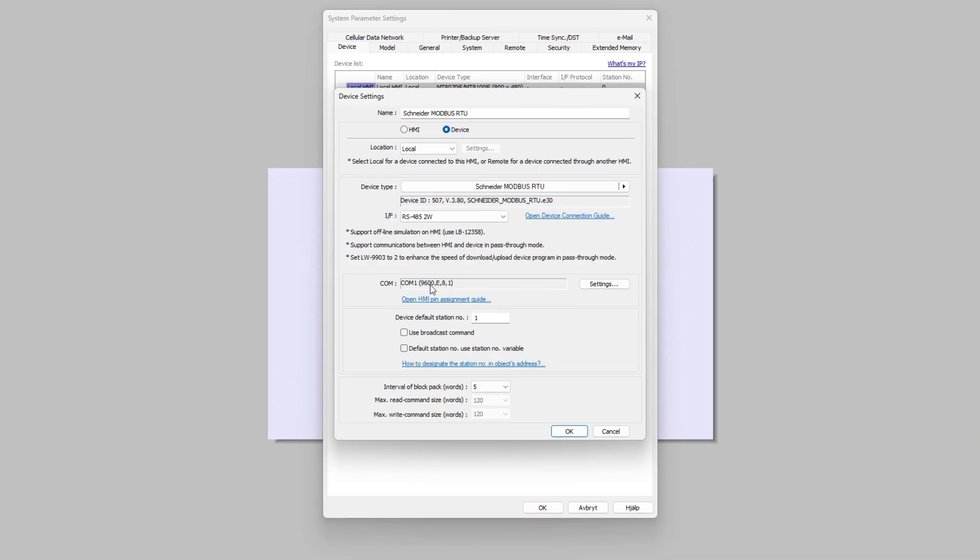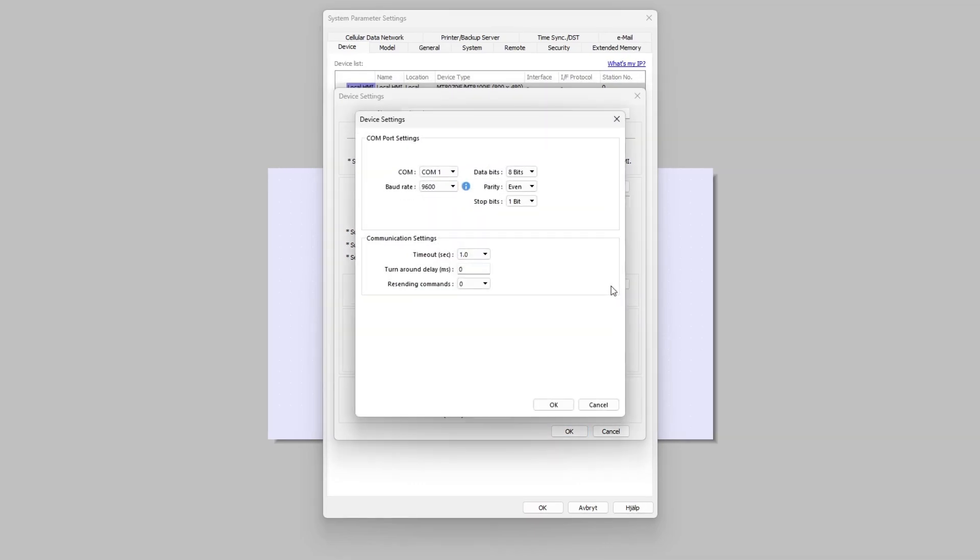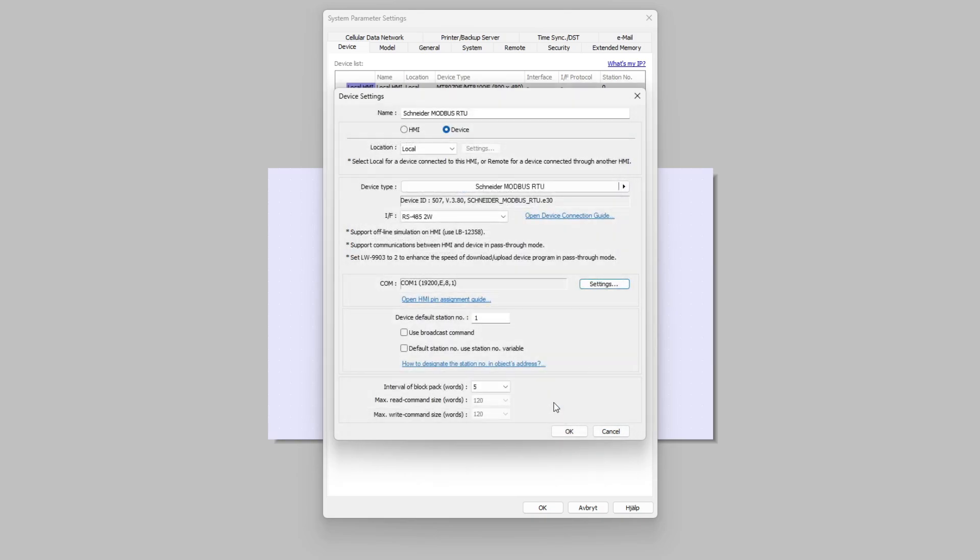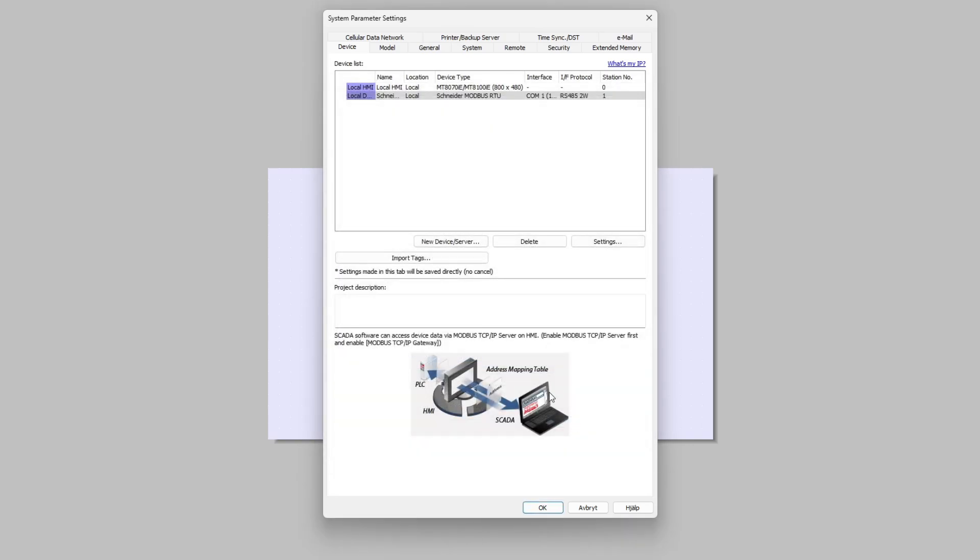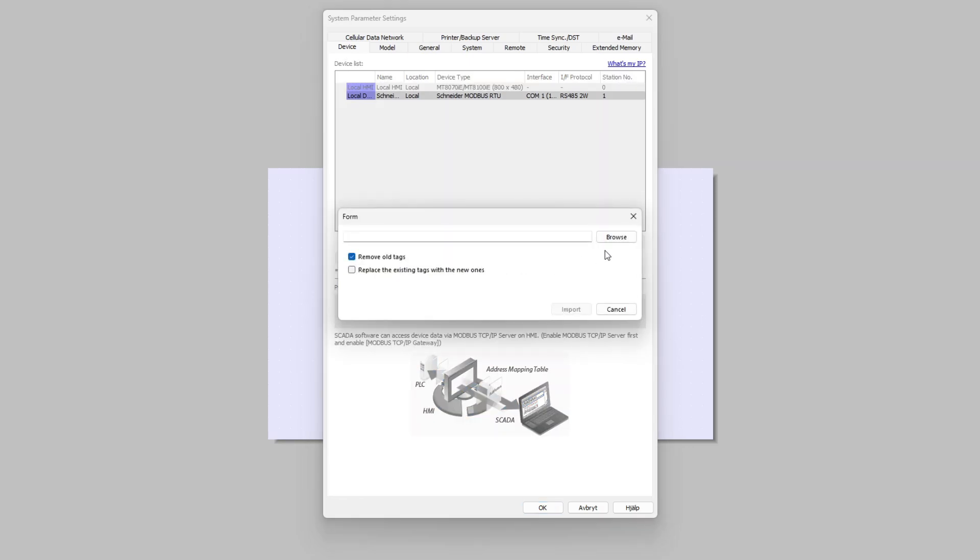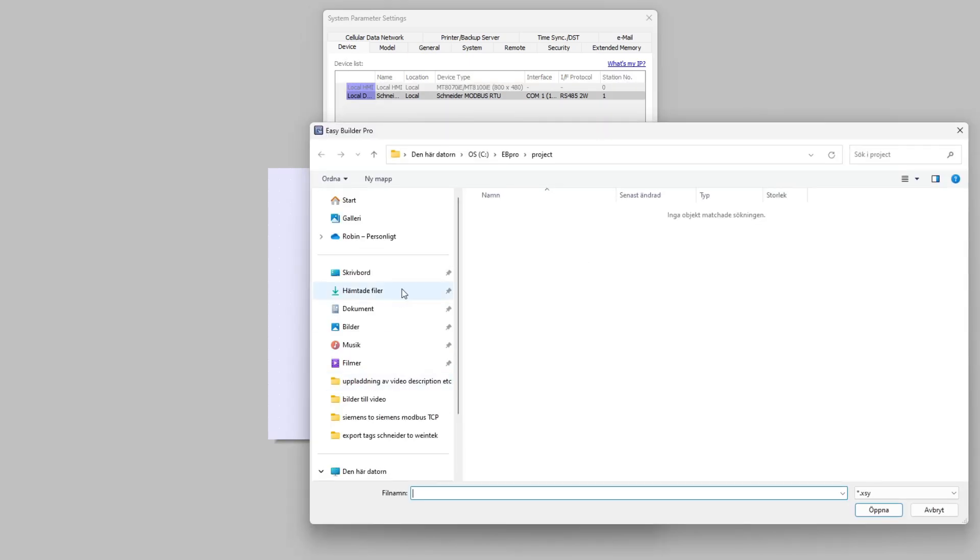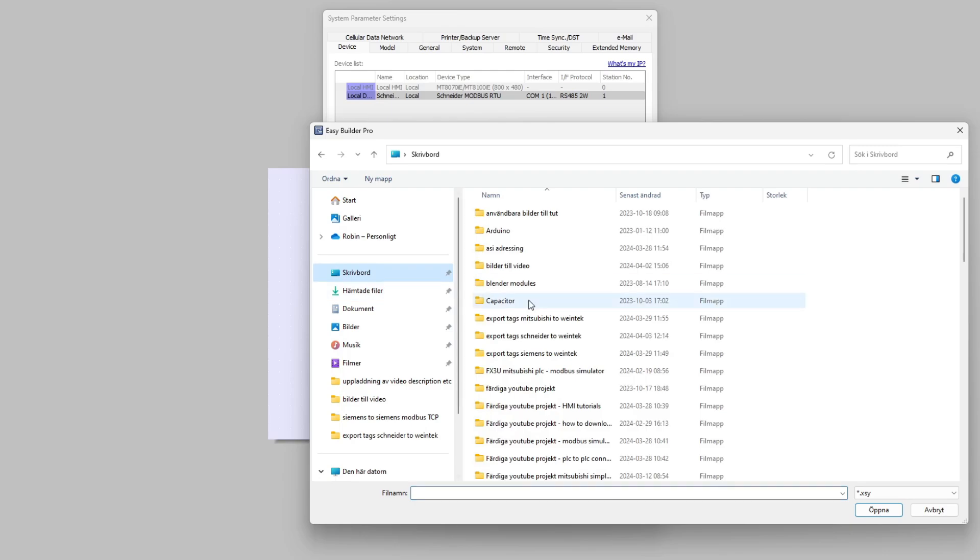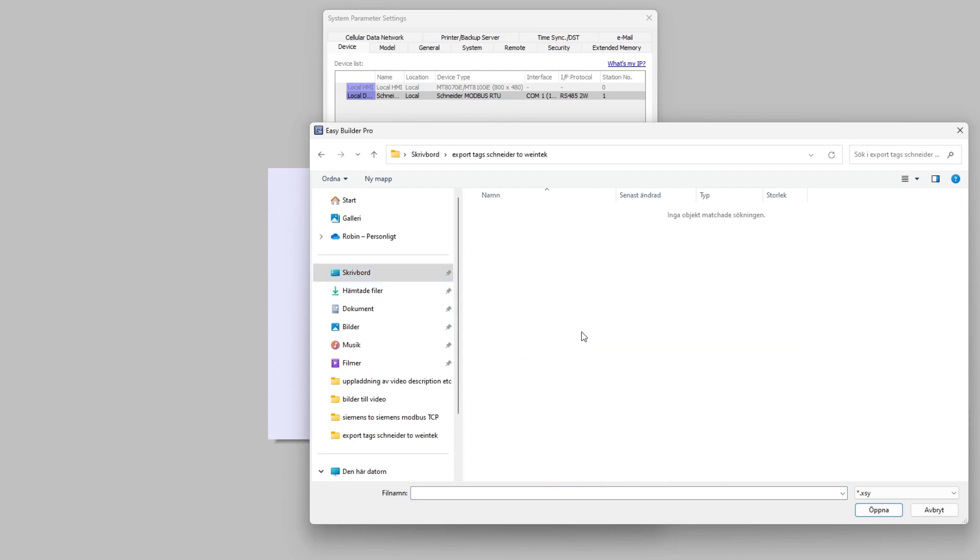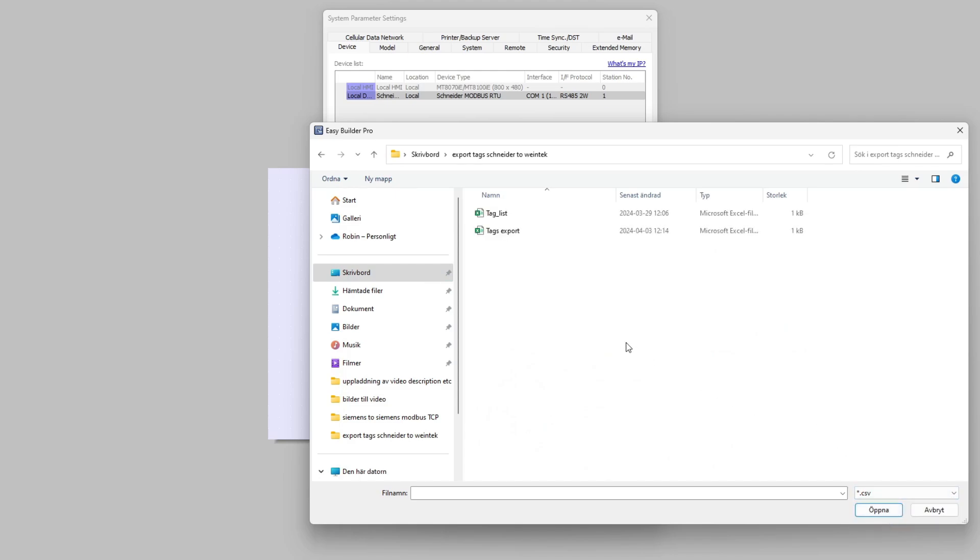We then want to click on Settings and change to the correct baud rate. Next we want to add the tags to the project. To do so we click on the Import Tags button. Then we click on Browse and find the map we added our exported tags list to. Then choose the right file type which is CSV file, then click on Open and Import.